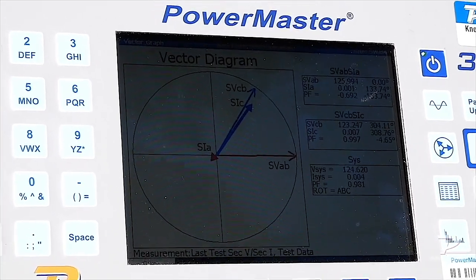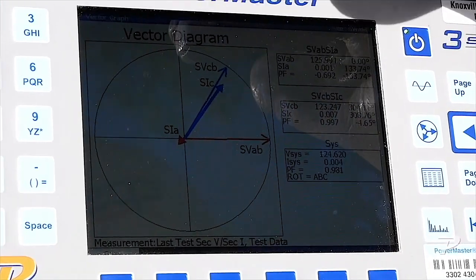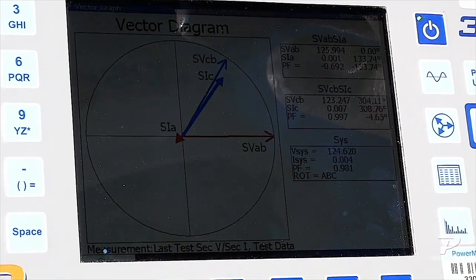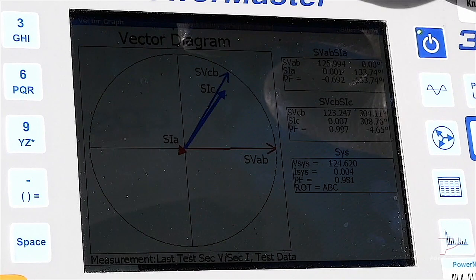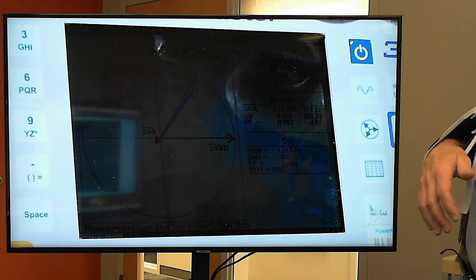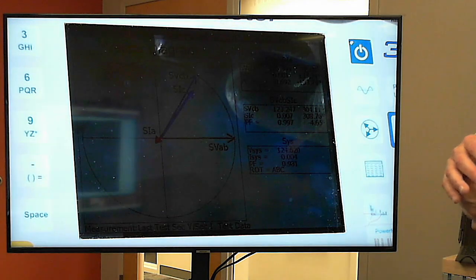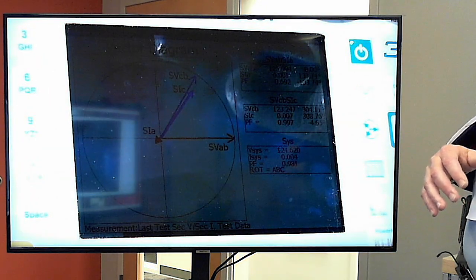Let's look. Unfortunately, so yeah, when you see this, we talk about this all the time. You've heard me say it a bunch, that high C leg, if you don't have any load on it, if the elevator's not running, or whatever it is that you've got on that high C leg, if it's not running, then you got a problem testing it, right? There's no load. Here we get into a situation with no load on the CTs, and we know what happens. It's not going to test them. It's going to start giving you these error messages.